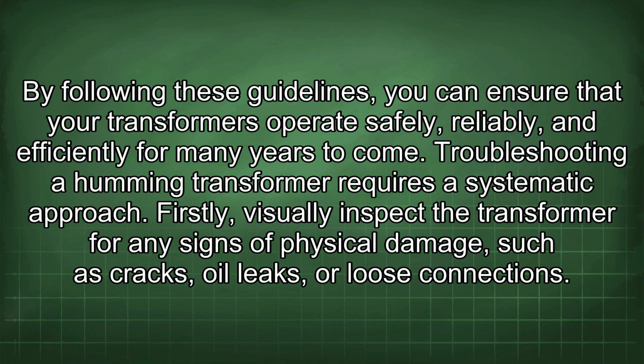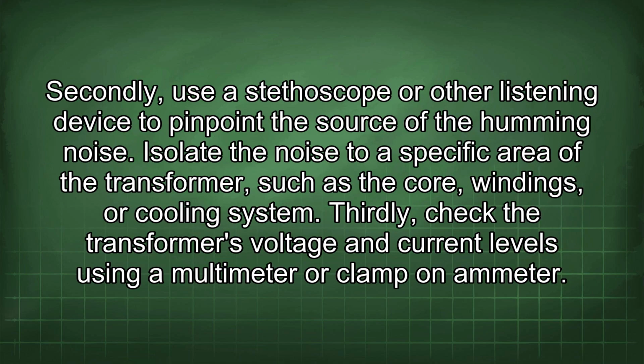By following these guidelines, you can ensure that your transformers operate safely, reliably, and efficiently for many years to come. Troubleshooting a humming transformer requires a systematic approach. Firstly, visually inspect the transformer for any signs of physical damage, such as cracks, oil leaks, or loose connections. Secondly, use a stethoscope or other listening device to pinpoint the source of the humming noise. Isolate the noise to a specific area of the transformer, such as the core, windings, or cooling system.